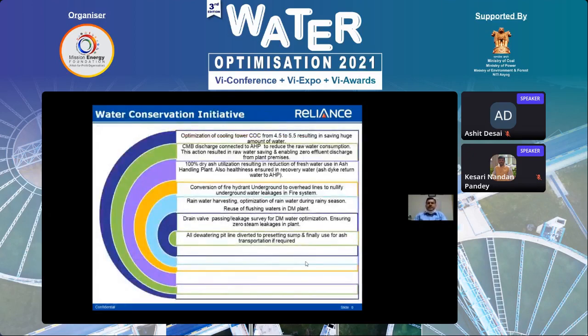These are the various initiatives we have taken. We have optimized our COC from 4.5 to 5.5, resulting in huge saving of water. CMB discharge was initially connected to the sump, but we have connected it to ash handling to reduce our raw water consumption. This action resulted in water saving. Since we are taking the continuous effluent plant water for use in ash handling, we are nullifying the discharge from the plant.